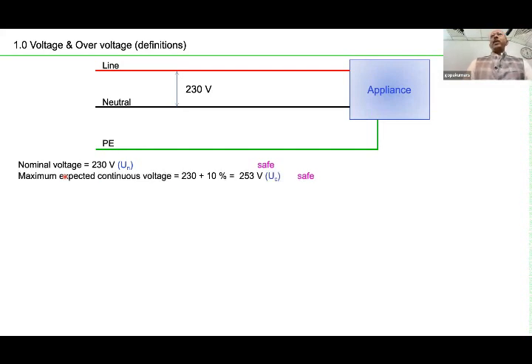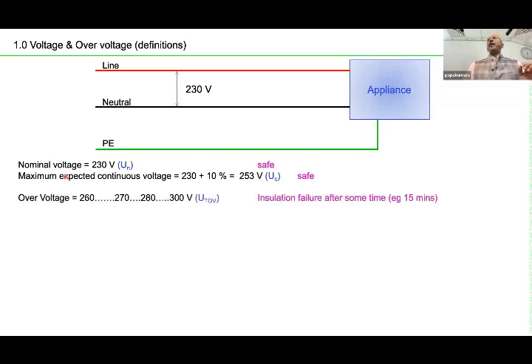Maximum expected continuous voltage. That means, out of this 230, how much voltage, for example, in a low voltage distribution system of a utility company. The transformer tapping voltage will be put a little bit higher, so that there is a voltage drop, and the last consumer also gets a voltage within certain limits. So if you look at the premises of the first consumer, probably the voltage is a little bit higher than 230 volt. That particular limit is what we call maximum continuous operating voltage. It is plus 10%. So you can put up to 10%. But of course, the voltage drop calculations and those things are also there. So under maximum continuous operating voltage, your equipment is supposed to be safe.